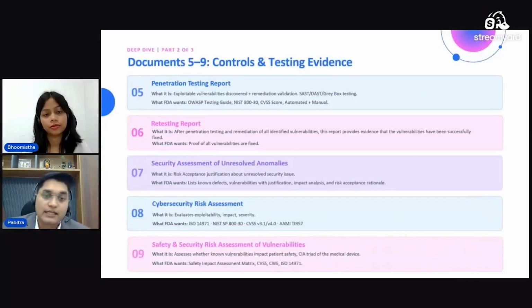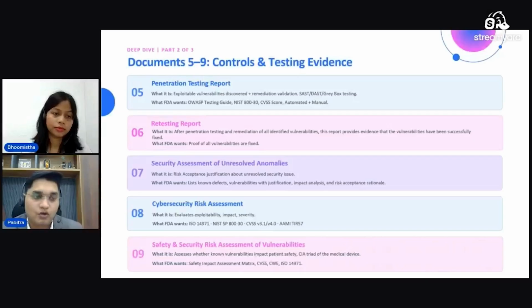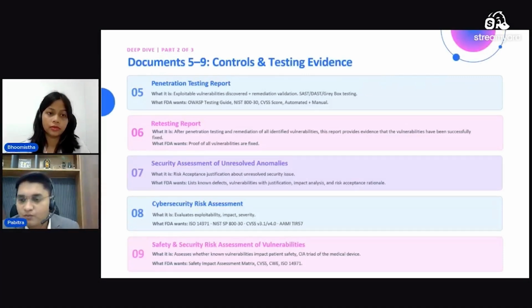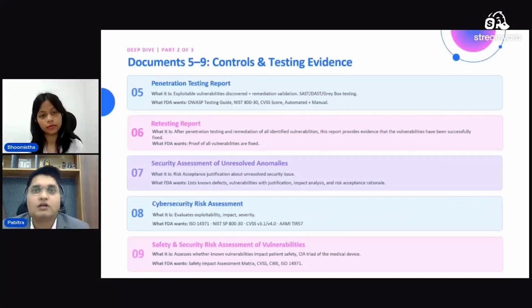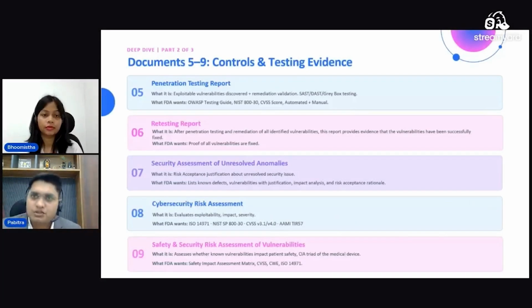And then there is the safety security risk assessment of vulnerabilities. This is also a new report the FDA is looking for right now. For a vulnerability, what is the impact on a patient, not on a technical component? For example, there might be an issue called DDoS, which is sending a lot of requests and jamming the device or the server. What will happen if DDoS happens on a heart rate monitoring device? The impact will be huge, because the patient data shown in the graph will fluctuate heavily. So the safety security risk assessment of vulnerabilities is now required by the FDA, and you can follow different standards like ISO 14971 for this.